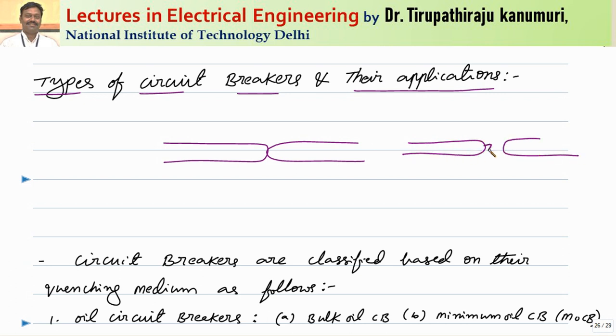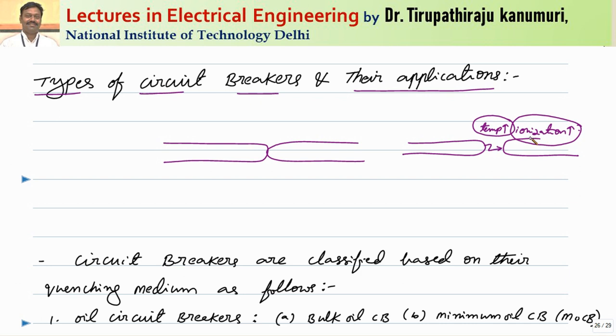When the contacts are separated, an arc is formed between them. With the formation of the arc, two things happen: first, the temperature will rise, and second, the number of ionized particles will increase — that means ionization will increase in the medium. Whichever medium is used in between, it should have the property that after natural current zero when the arc is extinguished, the heat stored there should be removed immediately and the deionization process should be initialized — increasing the dielectric strength and decreasing the temperature of the medium.